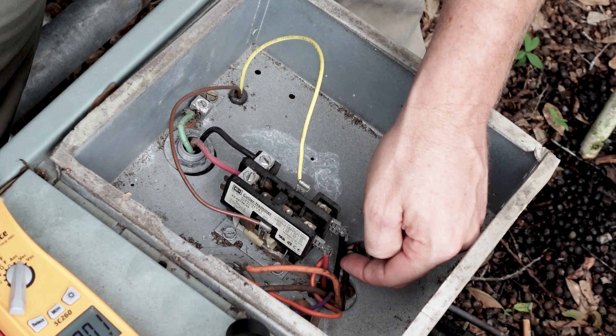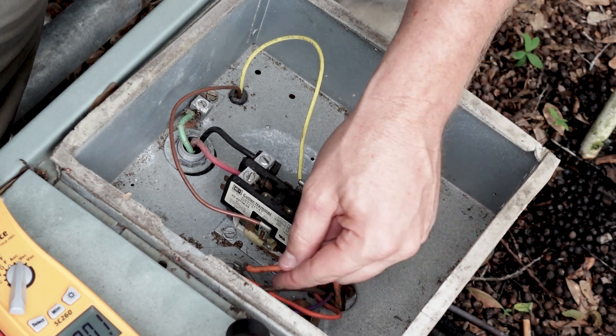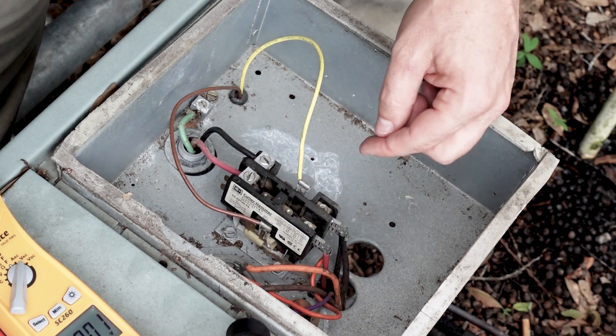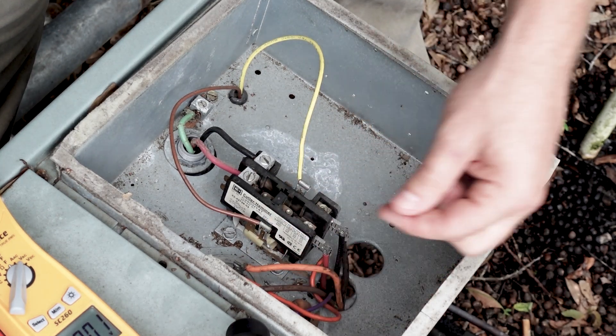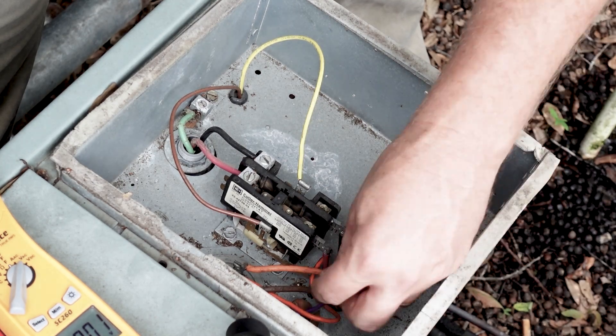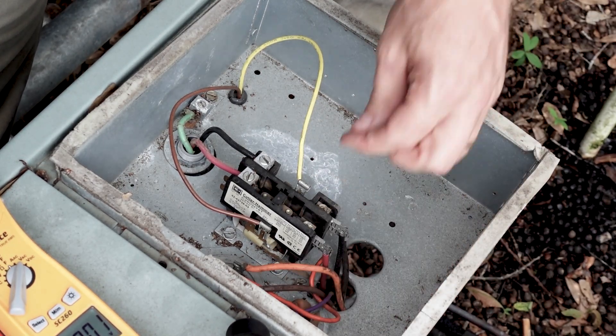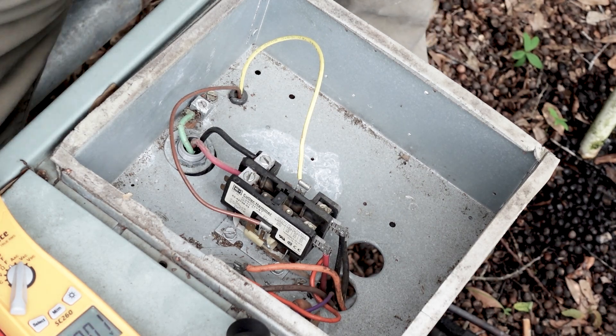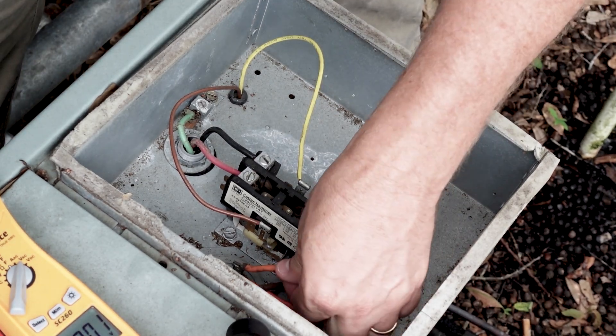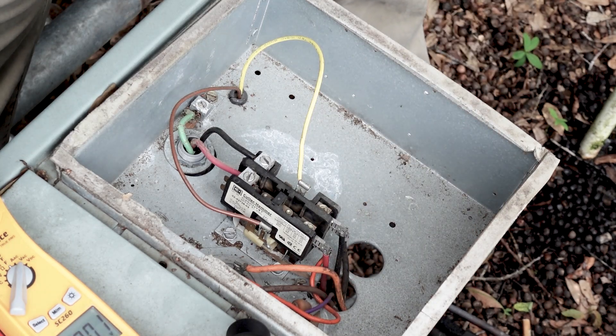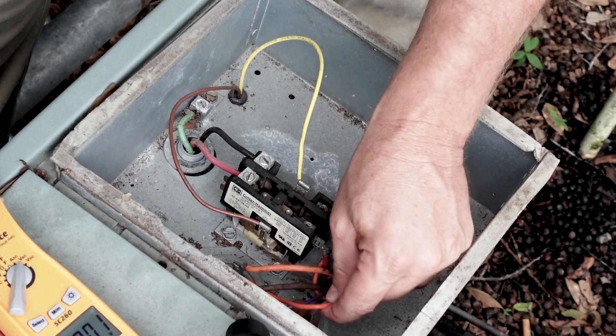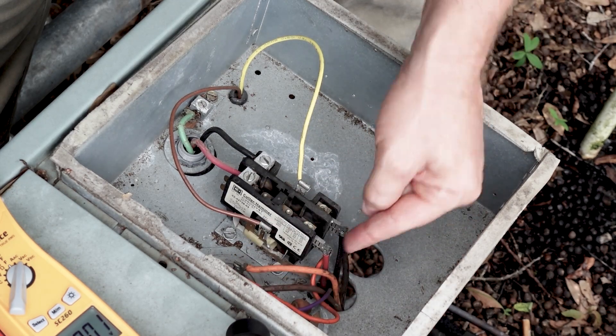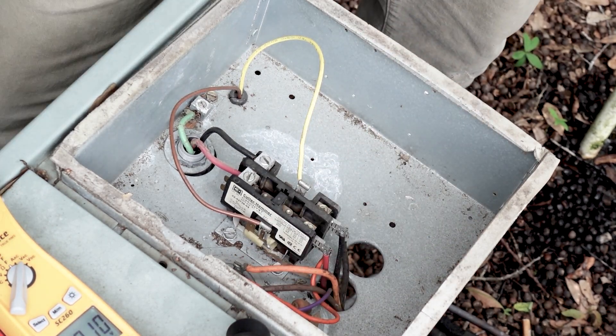And then this is a jumper that goes to the run side of the contactor, feeds the C side of the capacitor, and then coming out of this, the way this is set up, is our run for our condenser fan is coming off of that same C terminal, which is sometimes what you'll see. We could just as easily take this orange wire and connect it here if we had a spade there, because these electrically are the same point, because of this jumper that goes in between C and the run side of our contactor.